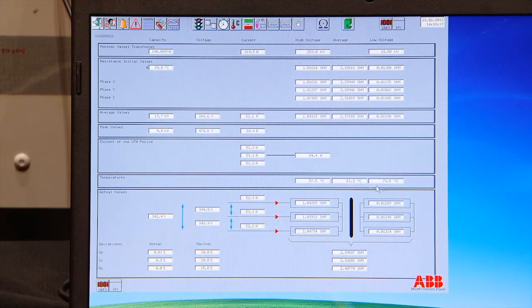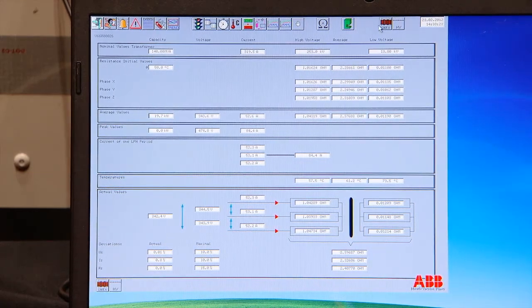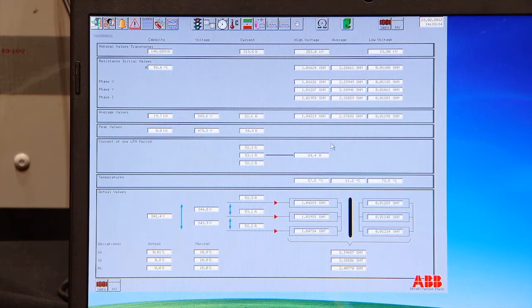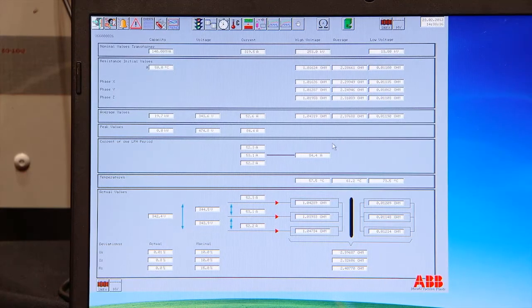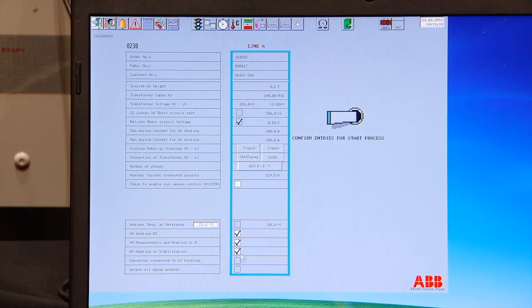So we are still at 73 degrees on the low voltage, 61 on the average. And since we are so high now at the low voltage, he will not do anything more at the moment. He will wait approximately 10 minutes, and then he will do another high voltage measurement, waiting for cooling down. To start with, you have selected here to do the high voltage thing in stabilization phase. If you deselect this now, then he will not do that. Then he will go for the average heating and behave more normal.